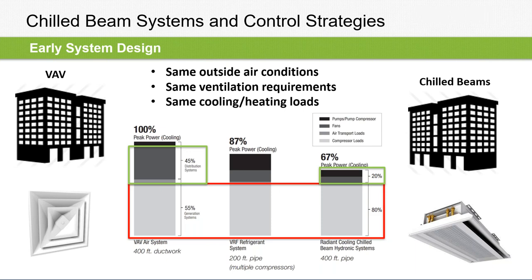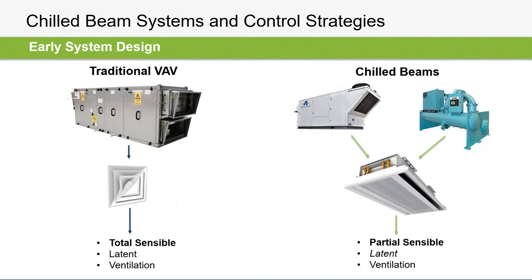So that's one way to think about these. The buildings don't change, but we're just trying to treat the same loads more efficiently with less airflow. So what that means for the system is that the air handler for the VAV system is doing all of the work for you. It's doing your entire sensible load, all of your latent load, and also your ventilation requirements.